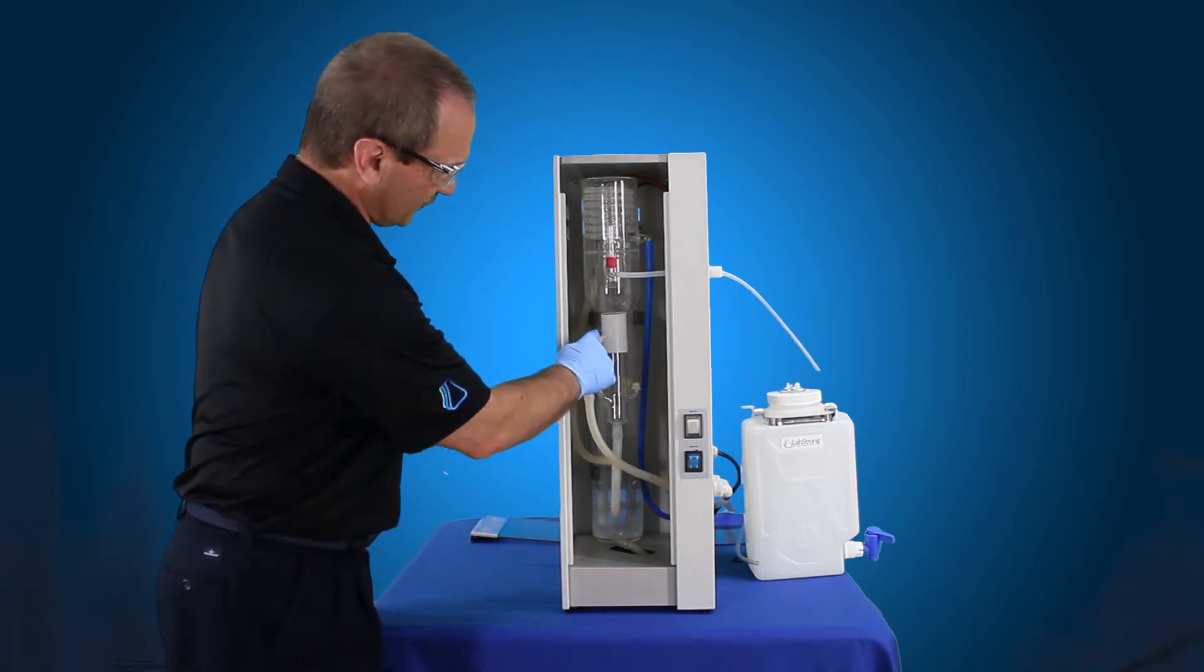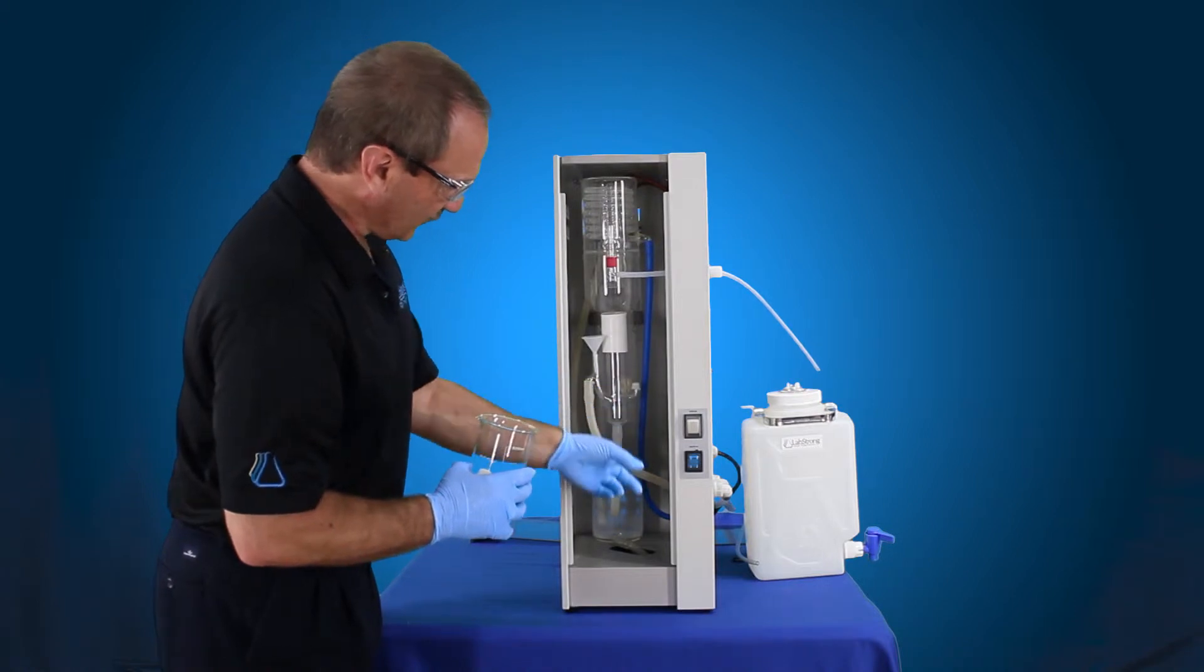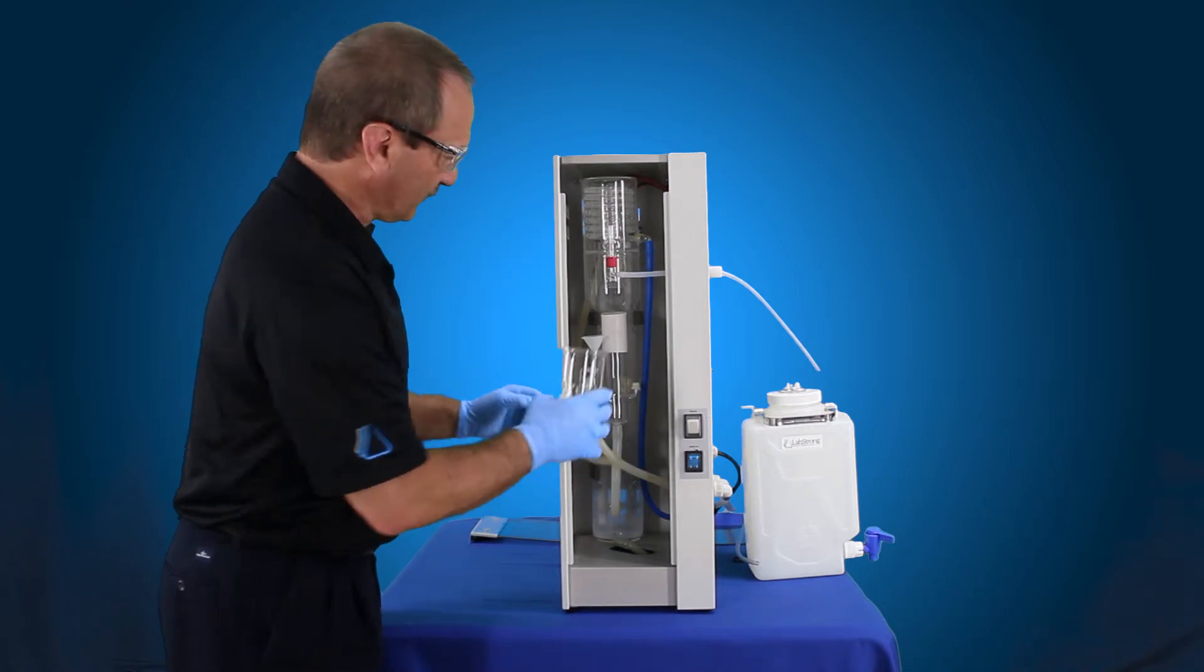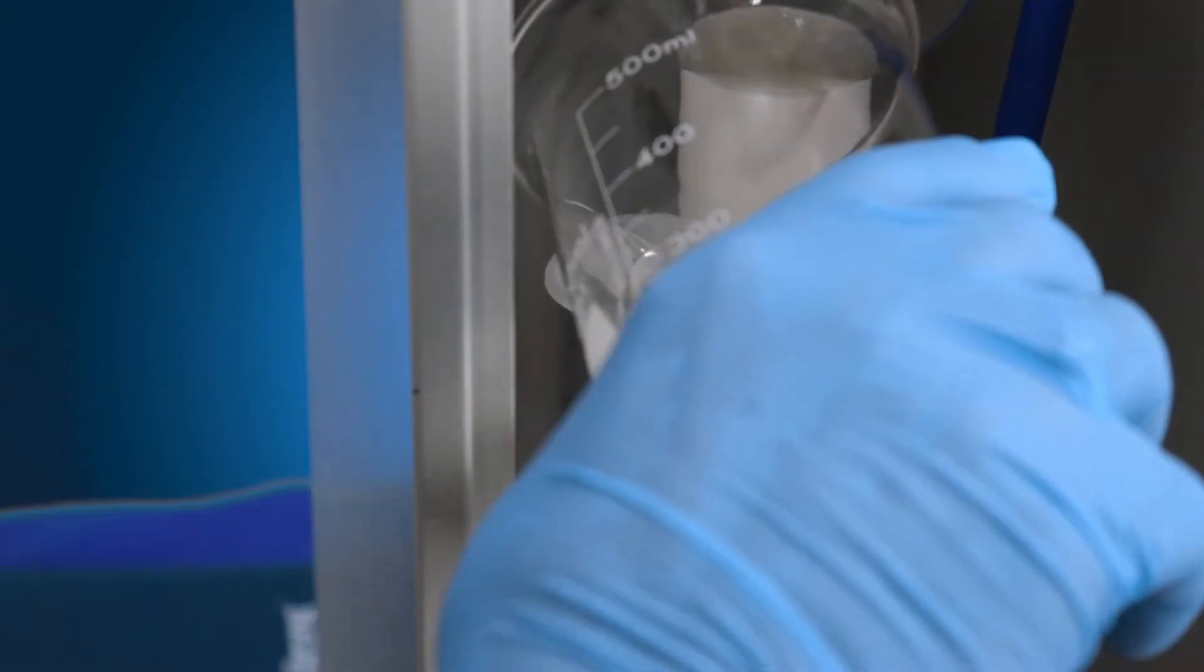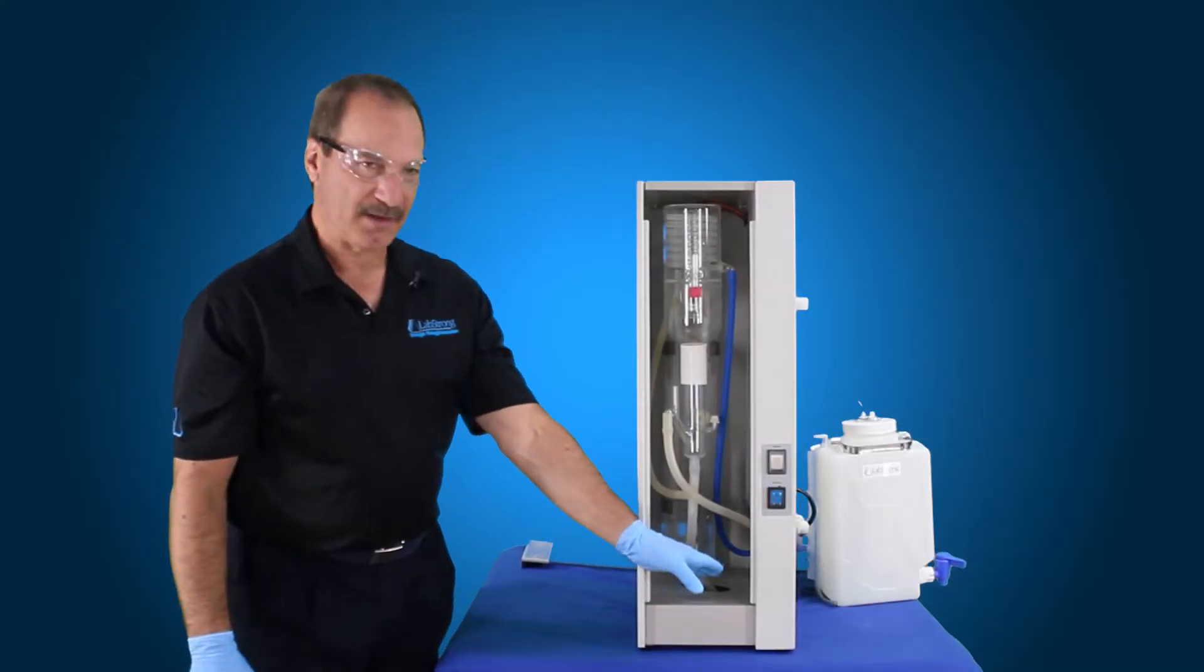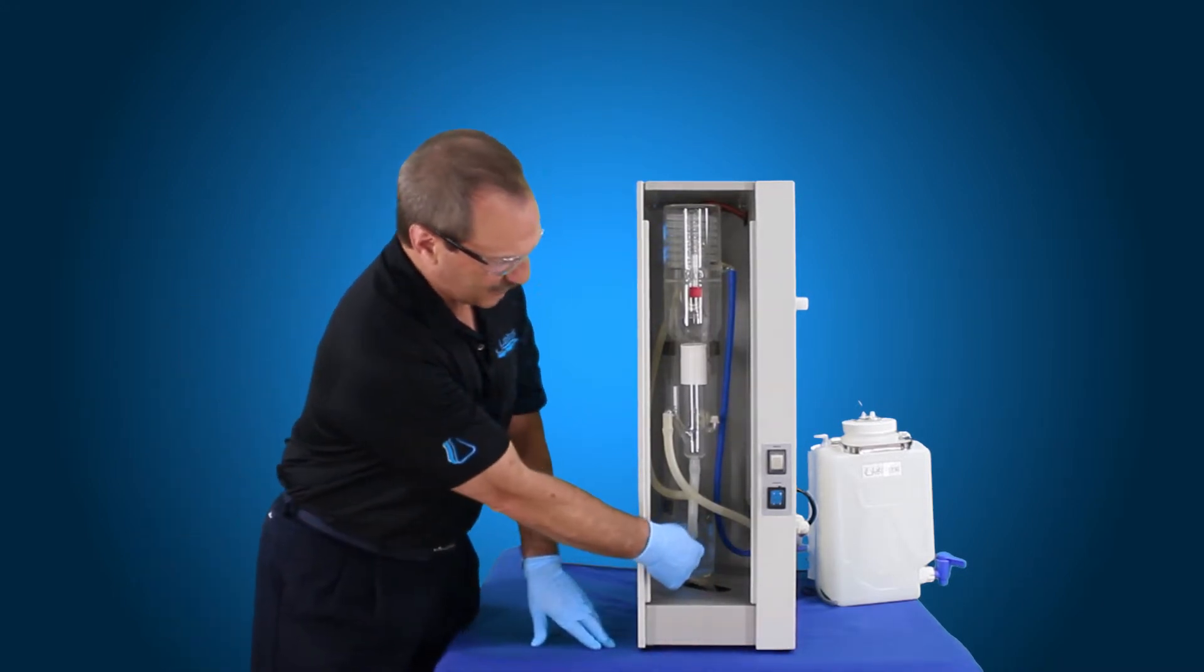The funnel goes into the vent port of our constant level device, which is eventually going to end up in the boiler, which is why you want the drain valve closed off. We're just simply going to start pouring that into here very slowly. It just takes a little bit of time and fills up the funnel.